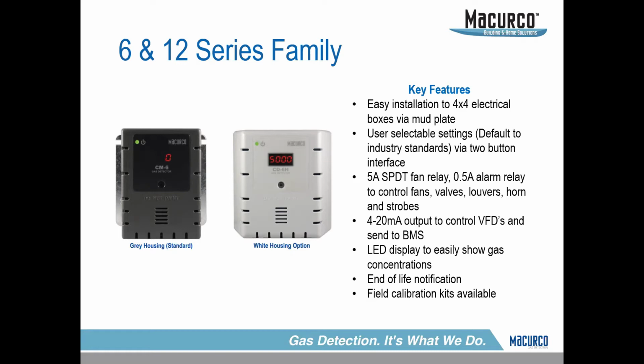The next one down is a 4 to 20 milliamp output. This is more of a communication protocol found in the HVAC world, but it's extremely common in the gas detection world. It is basically a linear increase. As your gas rises, so does your milliamp output. It's probably the easiest way to determine the level of gas concentration per your output. So a lot of people like to use that because it gives an actual scenario of what your gas concentration is at instead of just a dry contact relay.